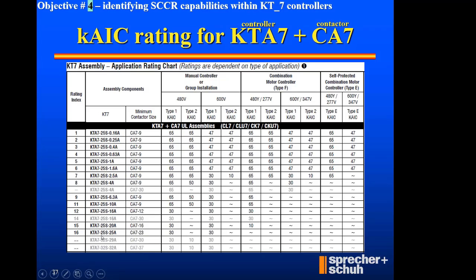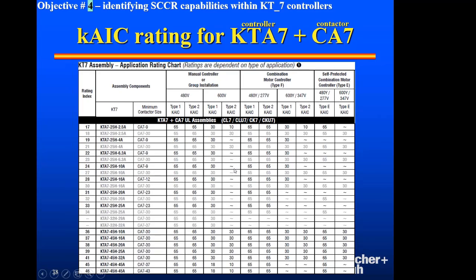This is the view of the 25S controller plus a contactor. It's all about using the table and how you're applying it and self-protected, those kinds of rules. You'll see that we can get type F, but can't get type E right here plus the contactor. So as I move to the next page and get out of the 25S standard, now I'm in a 25H high capacity. Here are the ratings if I'm going to use this high capacity controller, and here's the minimum size contactor. Now I've got a few more options. Now I can see what my capabilities are when I've got both the controller and the contactor. Down at the bottom, I basically reiterate the 45H plus the contactor. So these are both components. These SCCR ratings are located right behind the CL7 CK7 kinds of assemblies. So that's where that information is located.